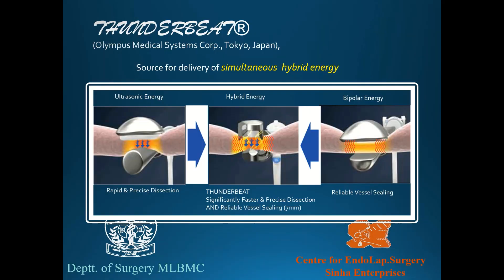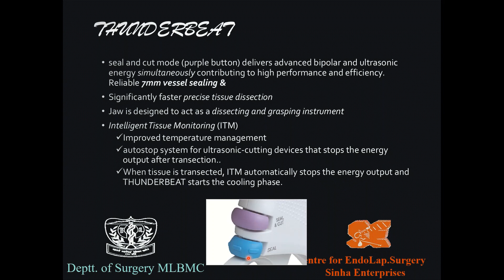When you combine electrosurgery with ultrasonic energy the result is the Thunderbeat — an instrument combining ultrasonic energy with bipolar electrical energy. The ultrasonic component allows rapid and precise dissection while the bipolar energy enables reliable vessel sealing. Together they provide faster, precise dissection and reliable vessel sealing up to 7 mm. The Thunderbeat probe has two buttons: purple for seal-and-cut, and blue for seal only. The seal-and-cut mode delivers both bipolar and ultrasonic energy.